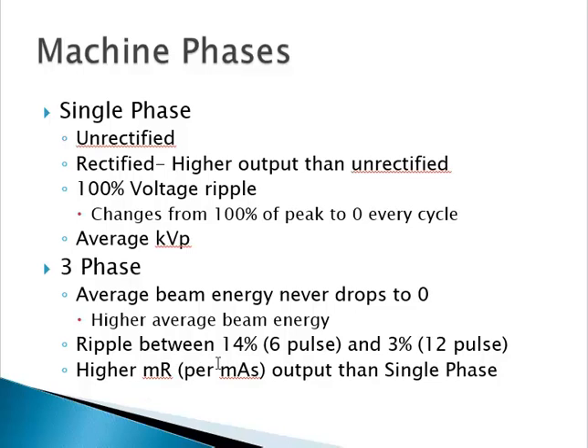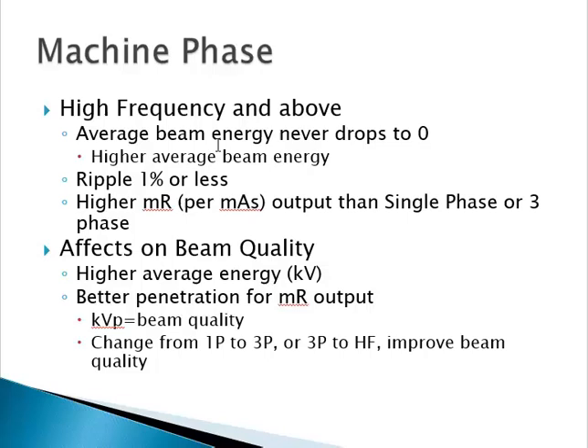High frequency pushes a bit further — everything said about three phase applies to high frequency, but voltage ripple is down to 1% or less. This gives an even higher MR per MAS output than even three-phase twelve-pulse. The effect on beam energy is higher average energy — peak energy remains the same, but average increases. This gives better penetration per MR output and a clear increase in beam quality. Changing from single phase to three phase, then from three phase to high frequency, each step improves beam quality.